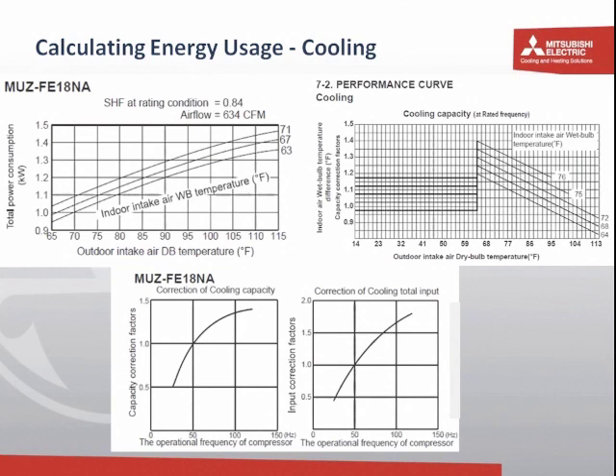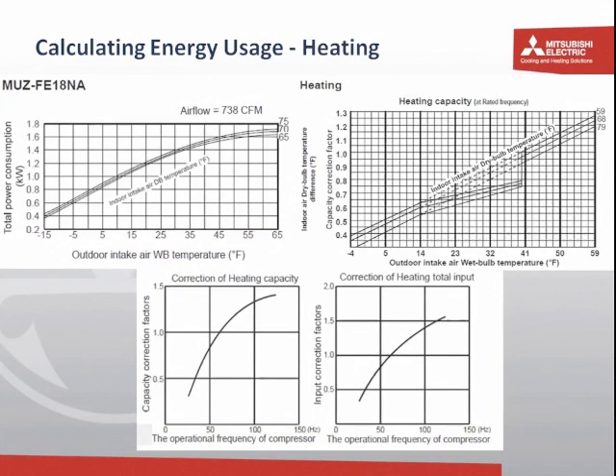And the architects that I've worked with in establishing these wattage usages have picked 4 spots, max, min, and then 2 in between. We've calculated the wattage at each and then made a weighted average of how many hours are likely to occur at each of those conditions and come up with the cooling input to the system. Similarly, those same features and data are available on the heating side, and again, pick the worst, best, and a couple interim spots, and we can come up with an overall heating wattage input. It's a little complex the first time you do it. What I've done is kind of held hands and worked with people as they go through it the first time, and beyond that, it tends to get pretty intuitive and it's easy to do on subsequent times. So I would like to extend that offer here as well.